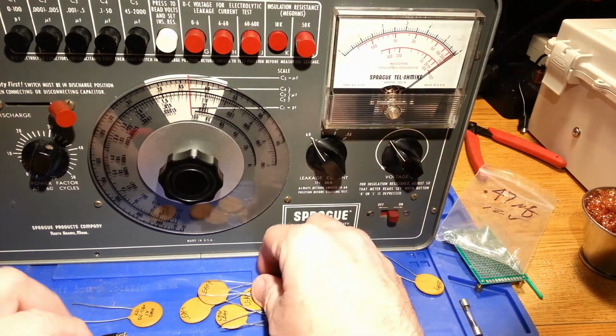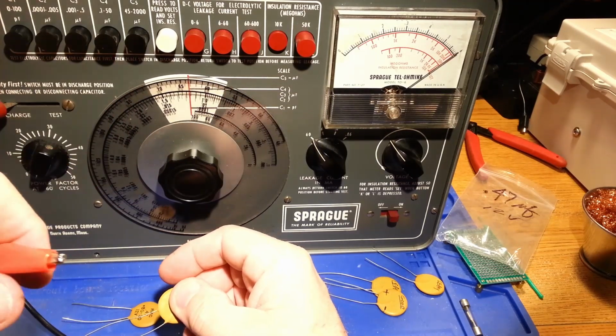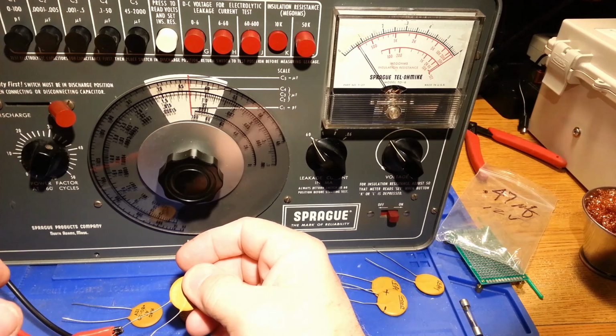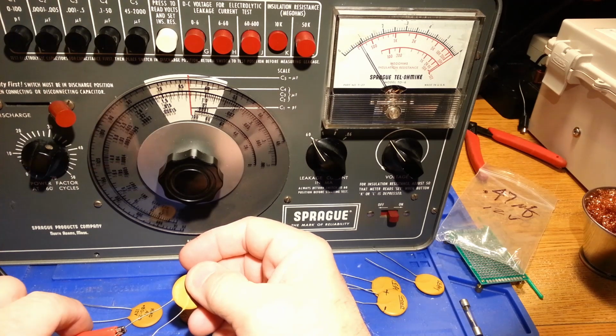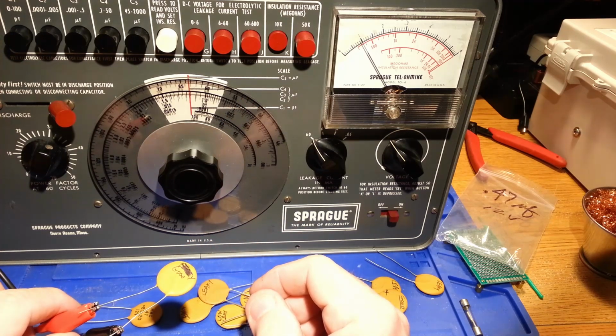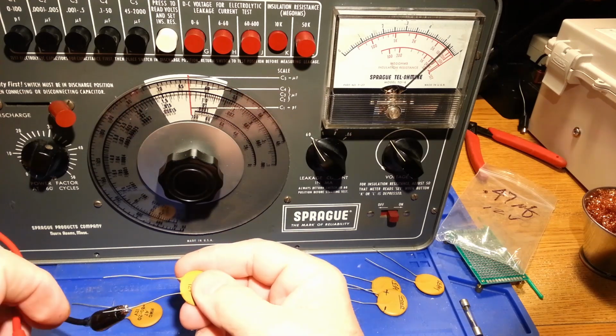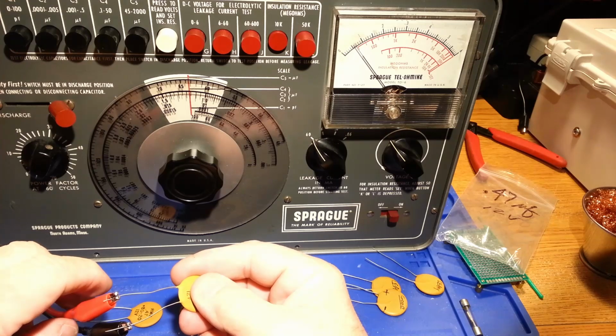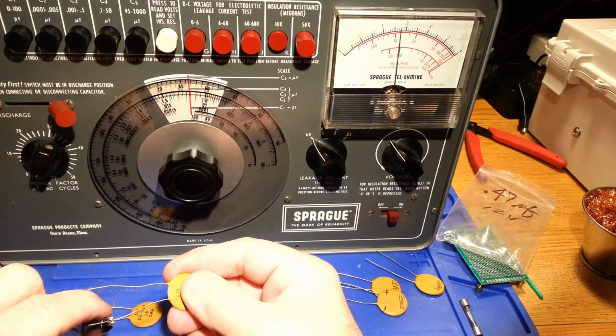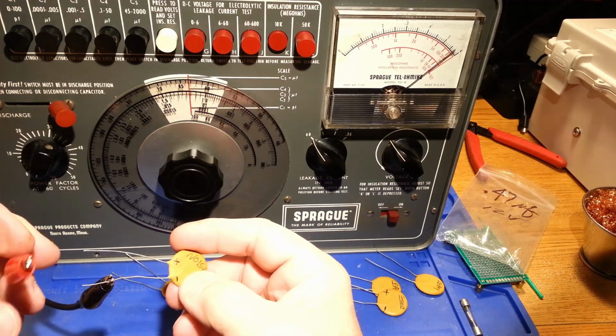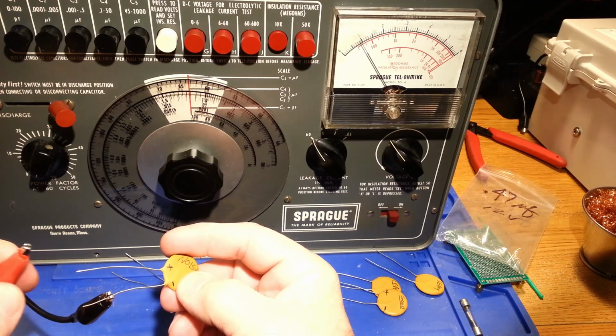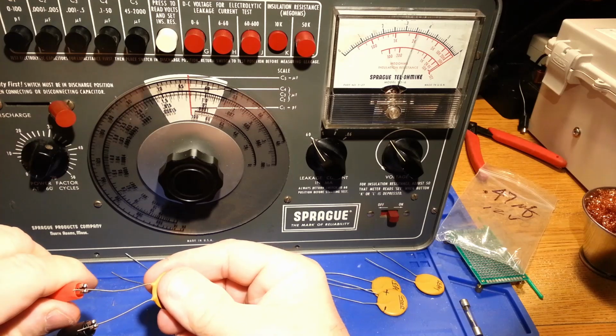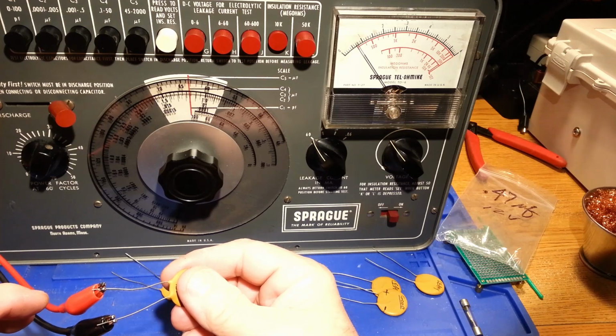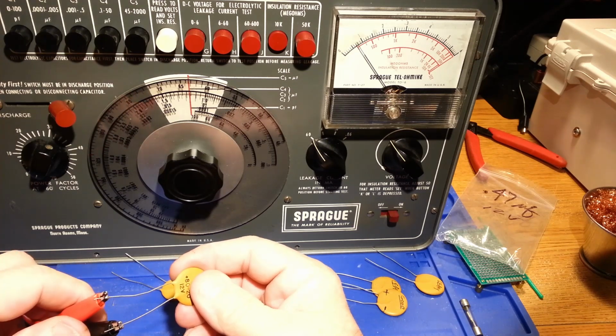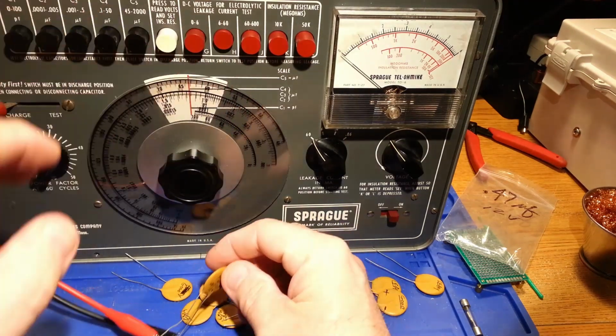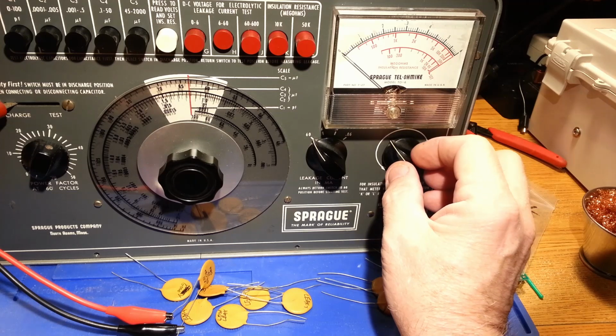So we're going to take another one, same batch. Lo and behold, it's got about the same results, but it's slowly going up. Curiosity, I'm going to reverse polarity on it. A little lower value in the other polarity. Let's get back to this one. This one's behaving about the same on the insulation resistance, but we're going to go to the function for measuring leakage current.